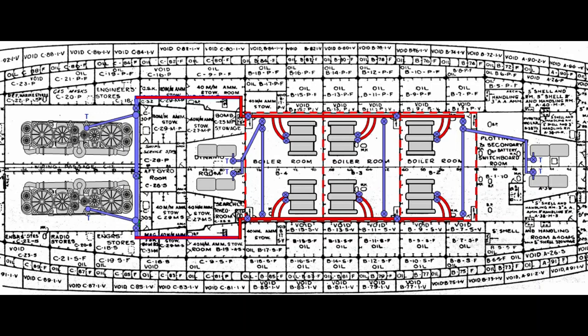Two large 14-inch steam mains extend along both sides of the boiler rooms and back to the engine rooms. Two feed lines connect each boiler to the main adjacent to it, and cross-connecting lines tie the two mains together in each boiler room and also the engine rooms. This creates what's called a ring main that will provide high volume, balanced steam and power to all equipment. We need to add stop valves throughout the system that can isolate boilers, boiler rooms, and entire sections of the system. And lastly, let's pipe into the engines and dynamos, then take a look at how the system was configured for battle and possible damage.